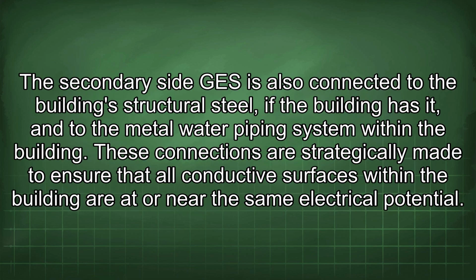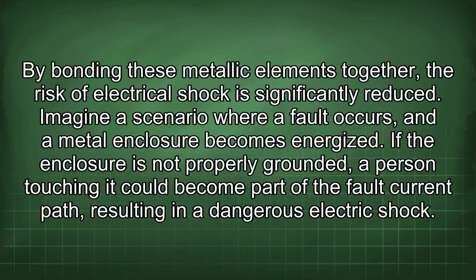The secondary side GES is also connected to the building's structural steel, if the building has it, and to the metal water piping system within the building. These connections are strategically made to ensure that all conductive surfaces within the building are at or near the same electrical potential. By bonding these metallic elements together, the risk of electrical shock is significantly reduced.